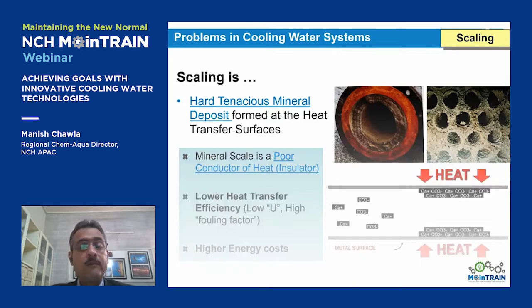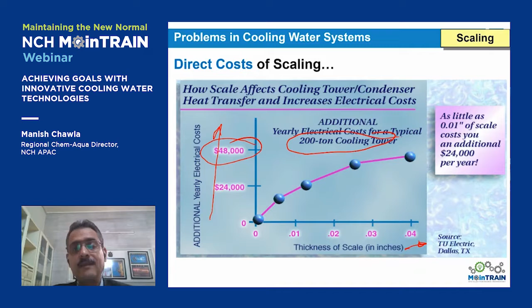For example, take a 200-ton chiller cooling tower. As the thickness of the scale keeps increasing, say from 0.01 to 0.04 inches—which is very little—the electricity bill keeps climbing up. For 0.04 inches, even in a 200-ton cooling tower, that could mean 48,000 US dollars extra in electricity. So it costs us a lot of electricity.